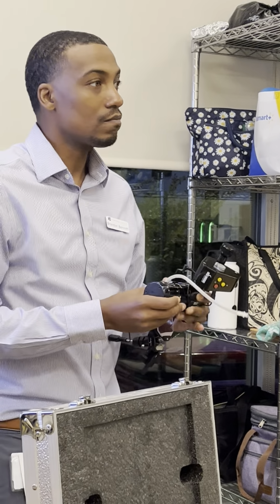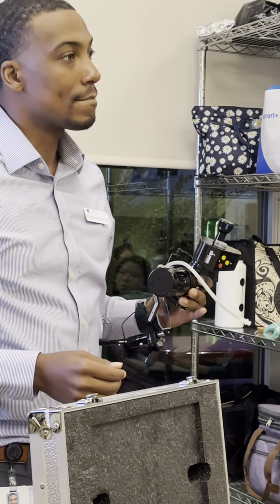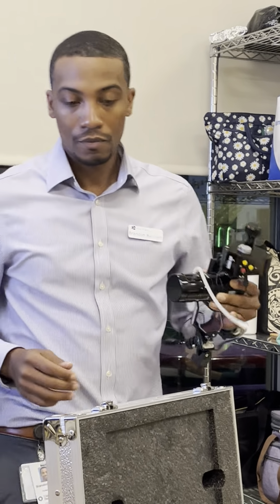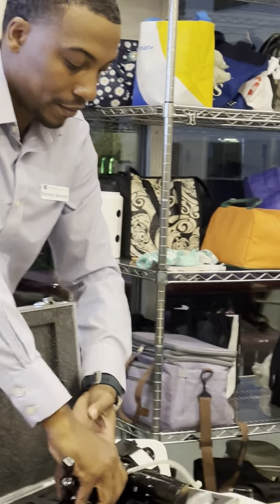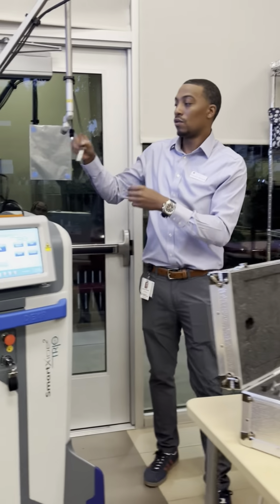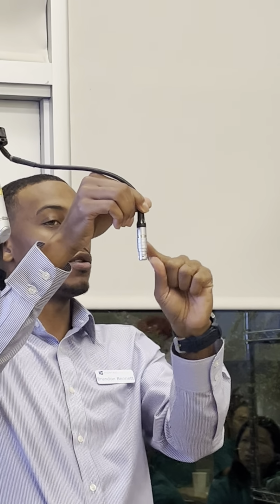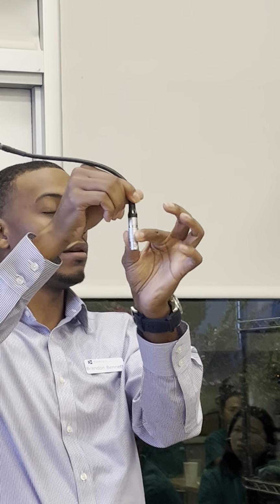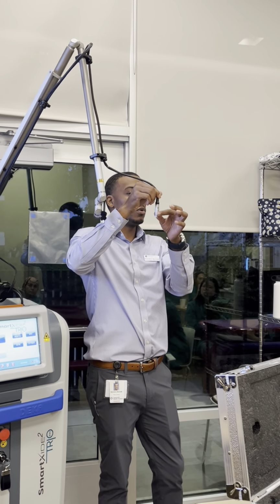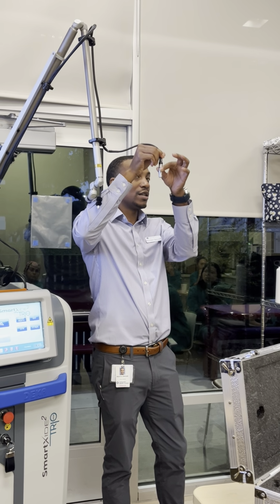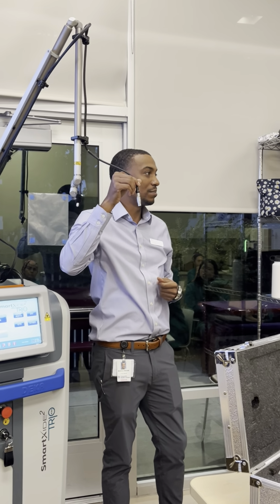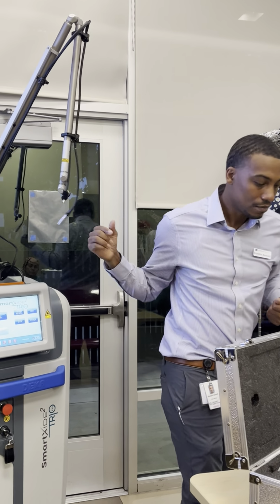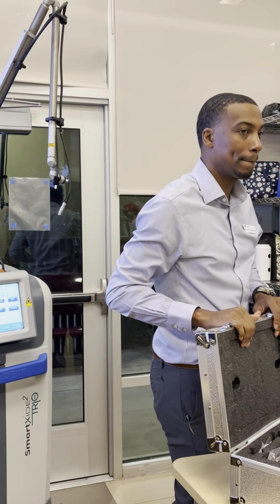In removing it, do you need to hold both ends together, or is there kind of a...? That's a very, very good question. On your cable, you have a depression ring. This entire ring moves up and down, and that will lock or unlock the communication cable from the micro manipulator. So as you pull up, it will naturally pull up and unlock. As you push down, it will snap into place and lock it into place. Very good question. Anything else before I continue on?